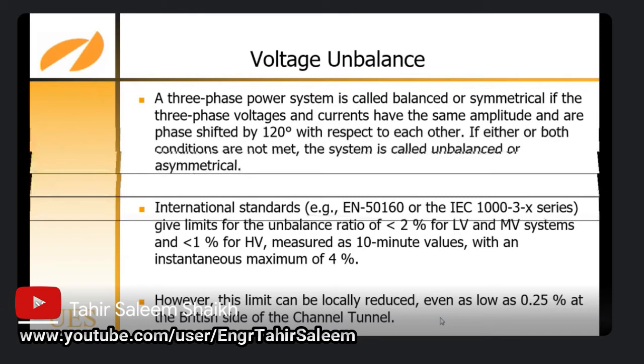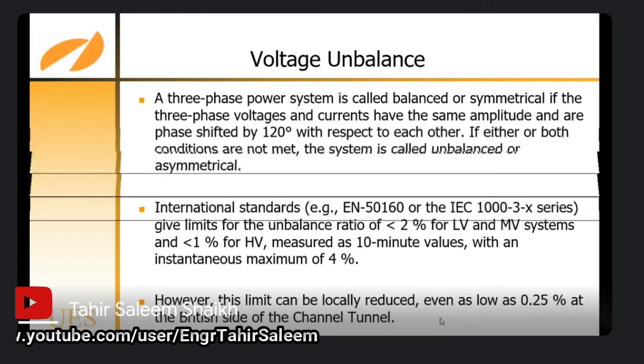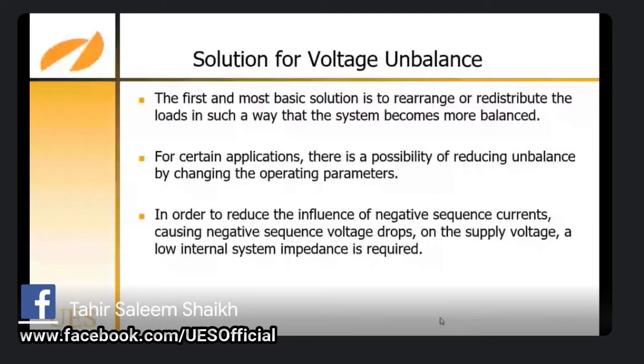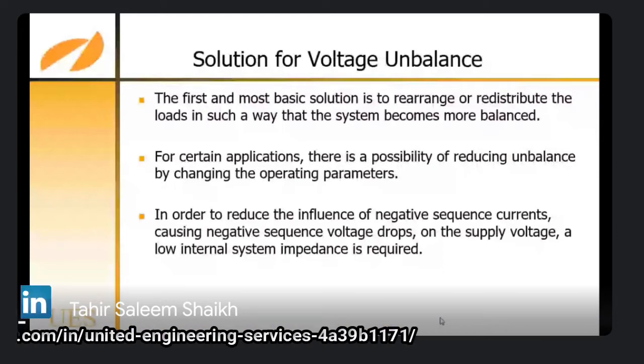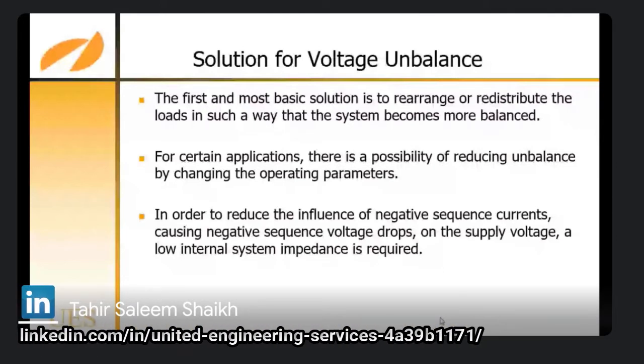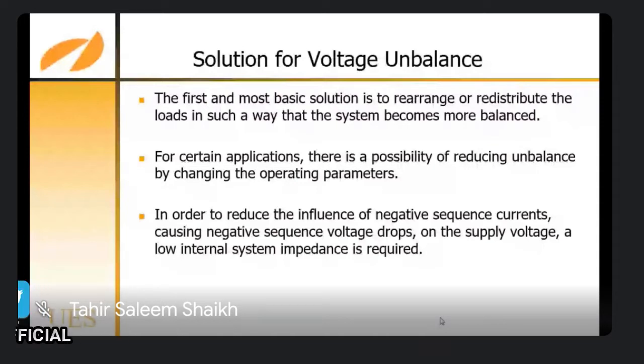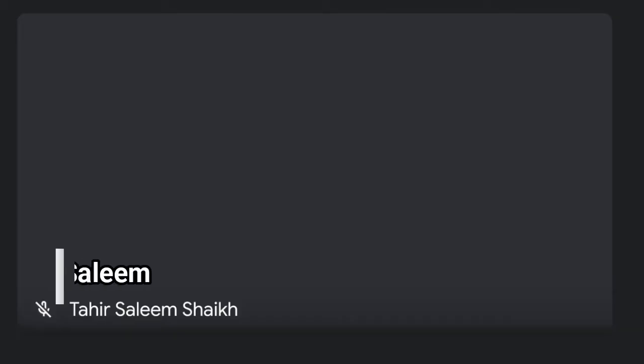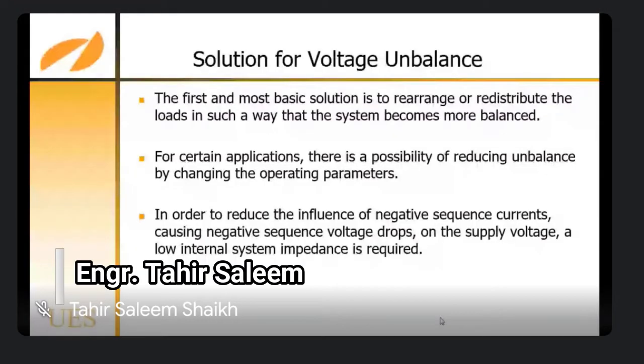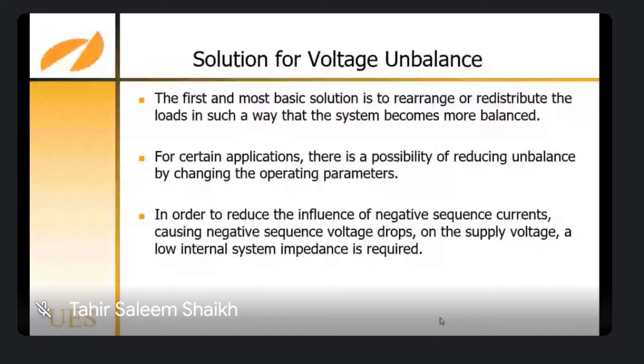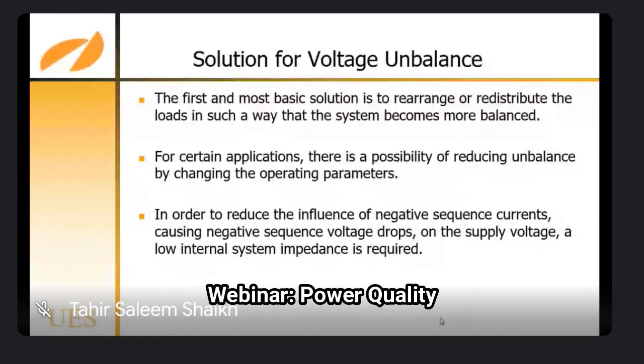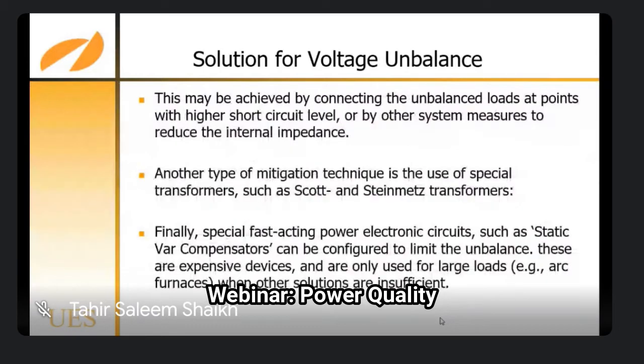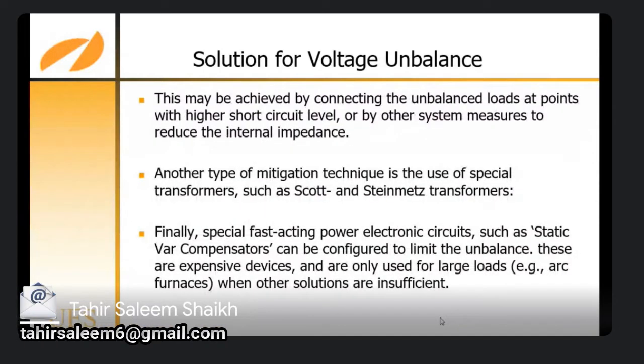The first and most basic solution is to rearrange and redistribute the loads in such a way that the system becomes more balanced. For certain applications, there is a possibility of reducing unbalance by changing the operating parameters. In order to reduce the influence of the negative sequence current causing negative sequence voltage drops on the supply voltage, a low internal system impedance is required. This may be achieved by connecting the unbalanced loads at points with a higher short circuit level or by other system measures to reduce the internal impedance.